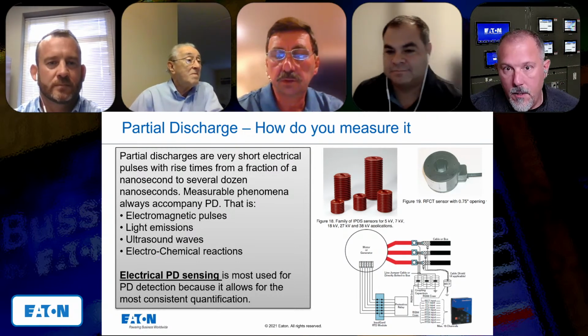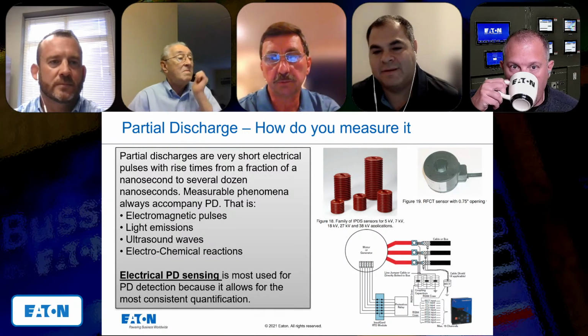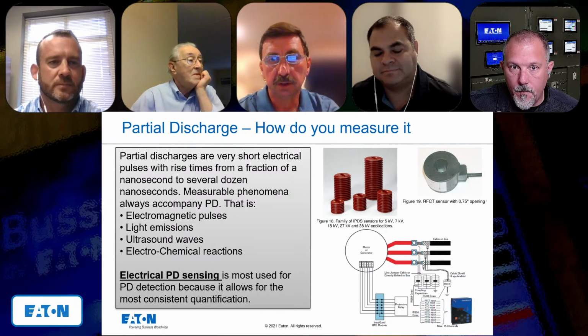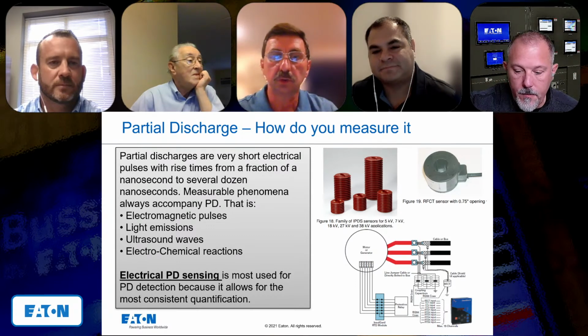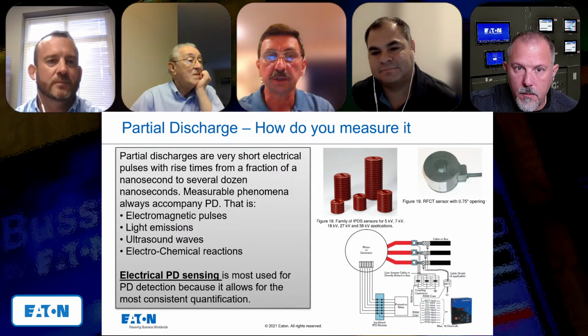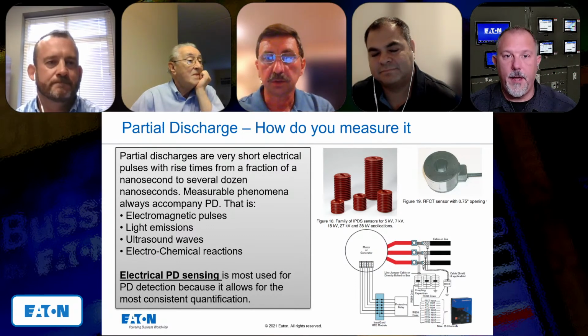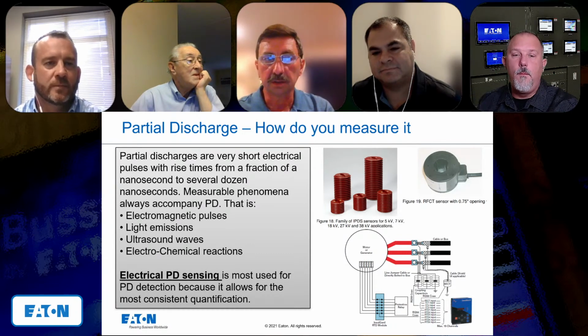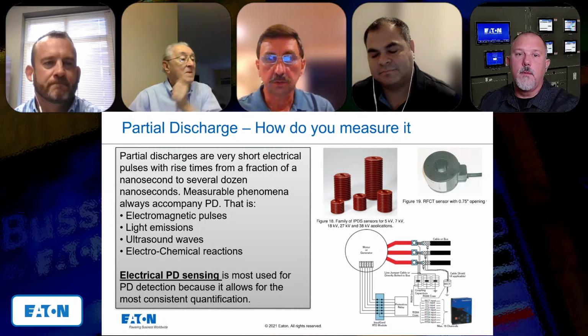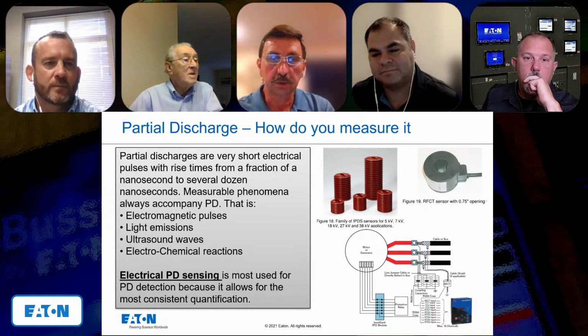Essentially, this is pretty normal to have partial discharge in insulation. It's just pretty common - if you have partial discharge, it doesn't mean it will break down immediately. The story is about how intense it is and how long it would last as it develops. It's not unusual, just pretty normal. You can see it practically anywhere.